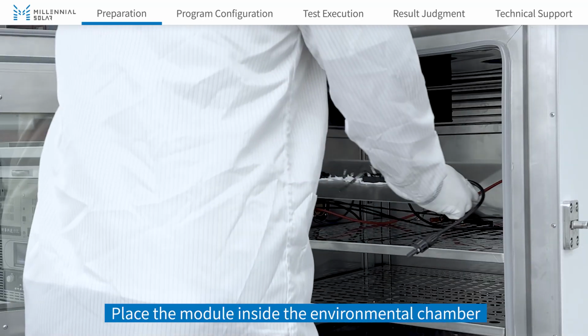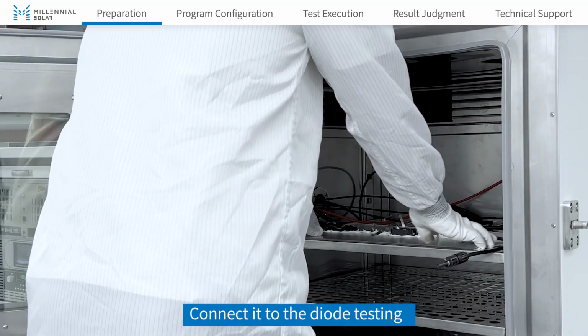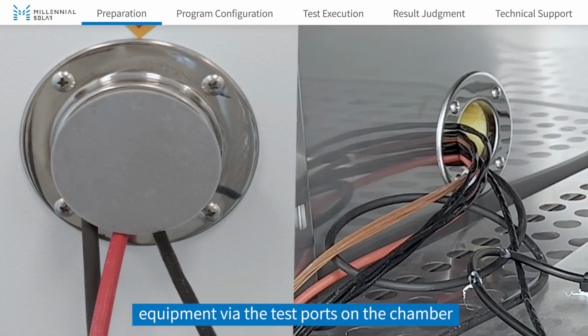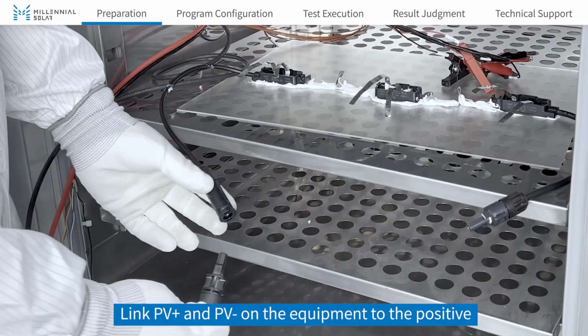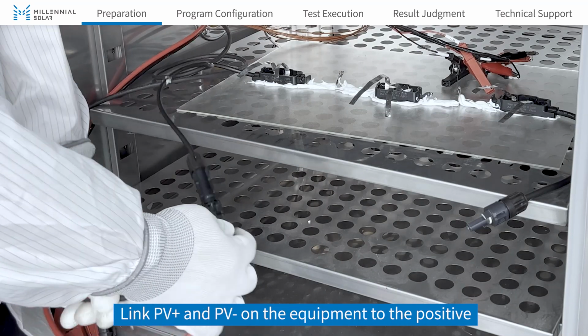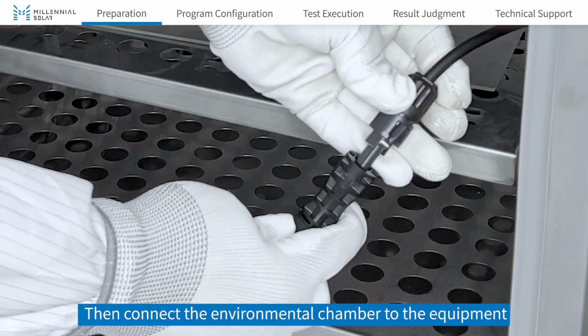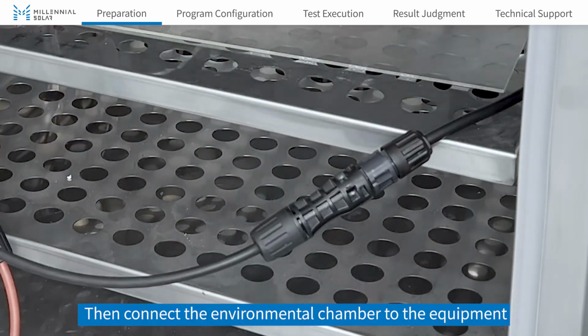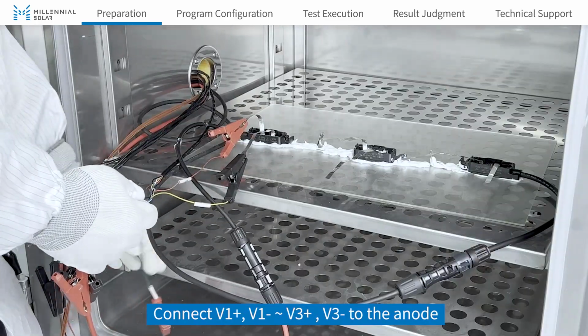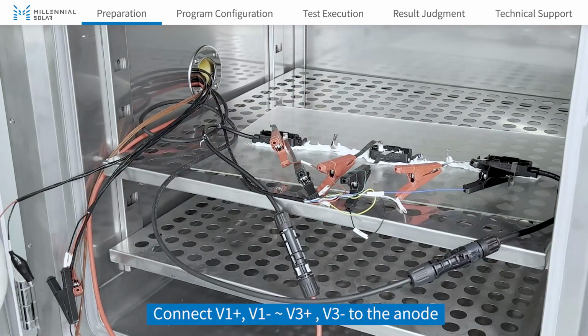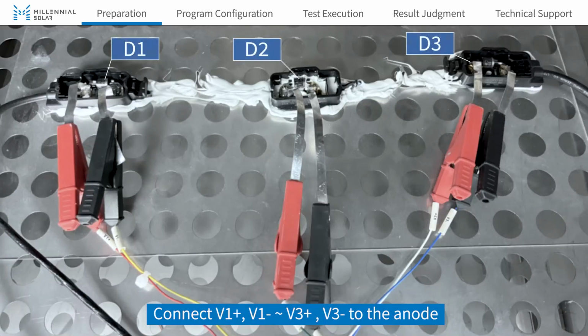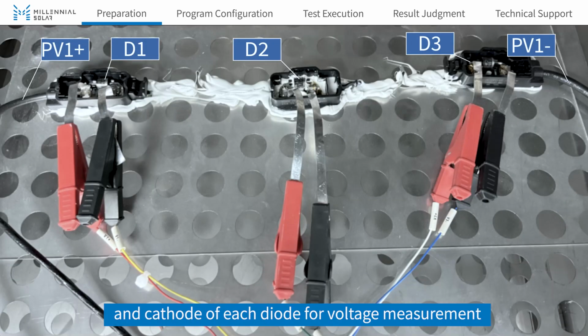Place the component inside the environmental chamber, and connect it to the diode testing equipment via the test ports on the chamber. Link PV+ and PV- on the equipment to the positive and negative terminals of the component. Then connect the environmental chamber to the equipment. Connect V1+, V1-, V3+, V3- to the anode and cathode of each diode for voltage measurement.